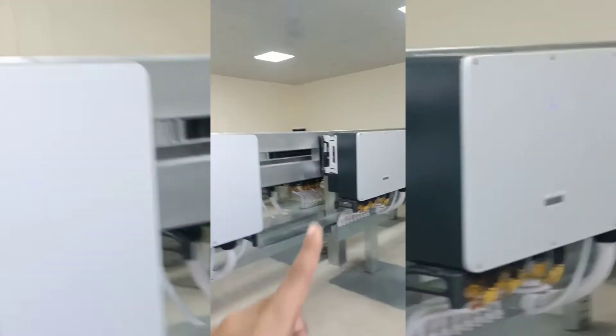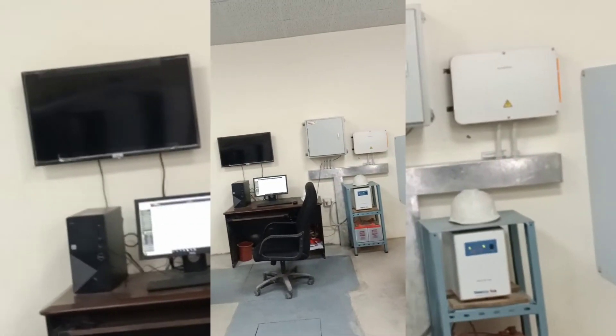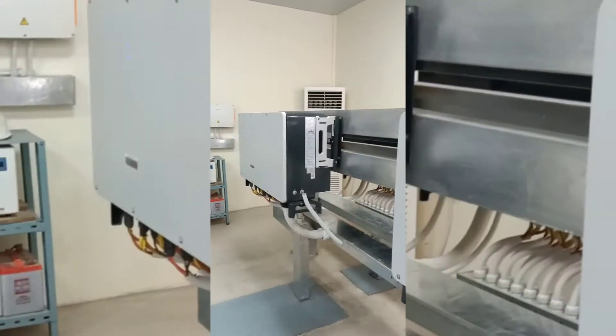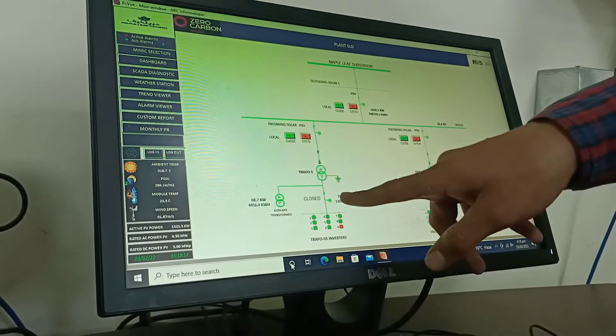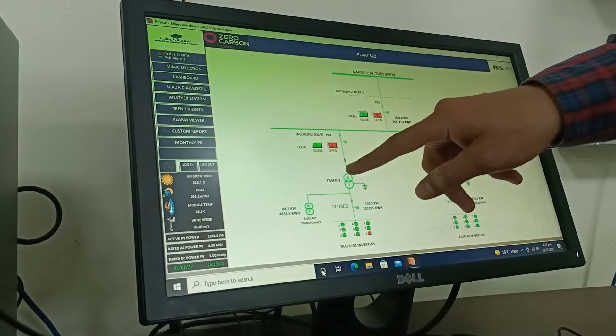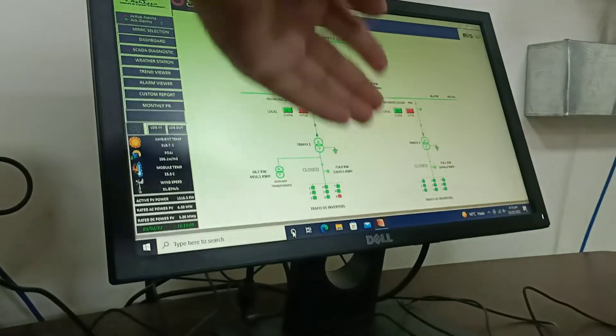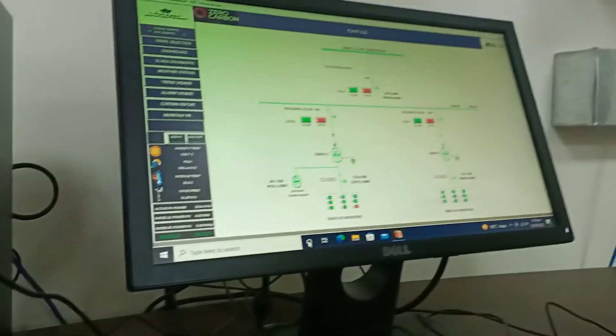So basically, this is one inverter — number one. Here you can see the inverter. These are the output wires connected from the inverter. We have two LV panels here. We have a panel in the unit as well. We are running at 800 volts, stepped up to 6.3 kilovolts, and feeding into the main grid unit.